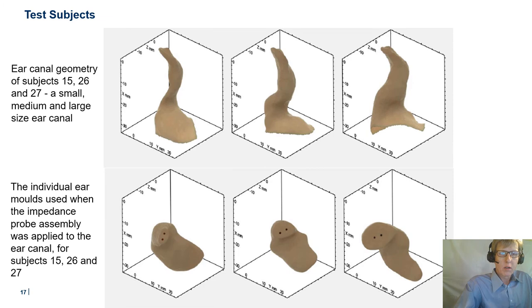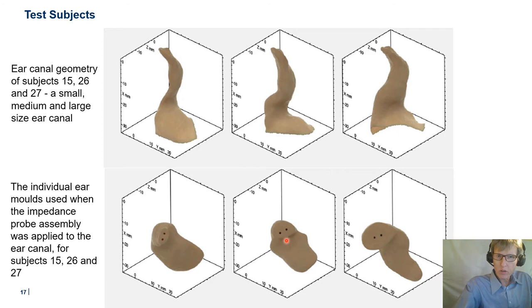To give an idea of the large variation in ear canal geometry, here's an example of a small, medium, and large size ear canal and the corresponding individual ear mold. The cross-sectional area at the measurement plane — the tip of the ear mold — is 17, 46, and 108 square millimeters respectively. The ear mold has two holes for the connecting tubes, placed with the same spacing and using the same tubes as when the impedance probe assembly was connected to the reference load cavities.